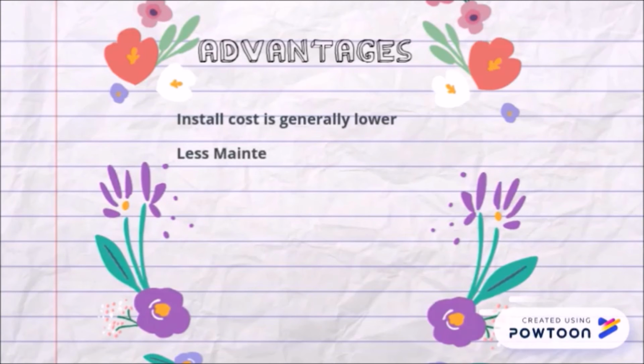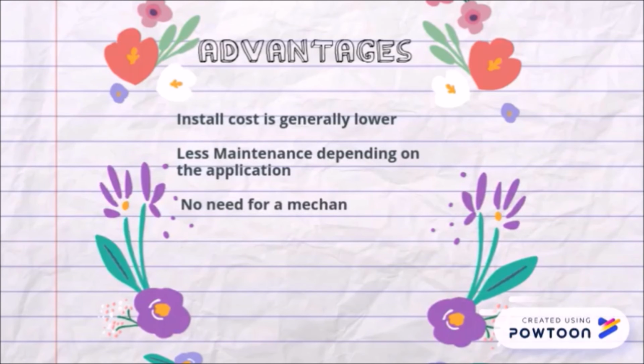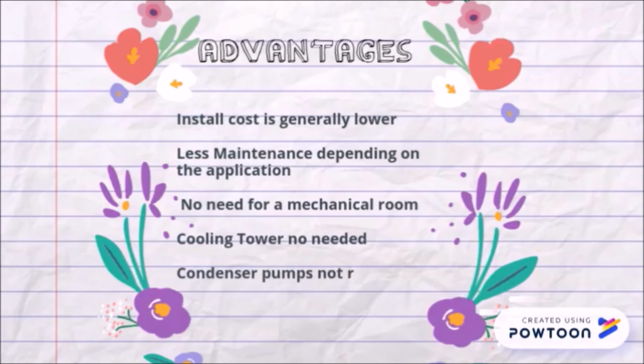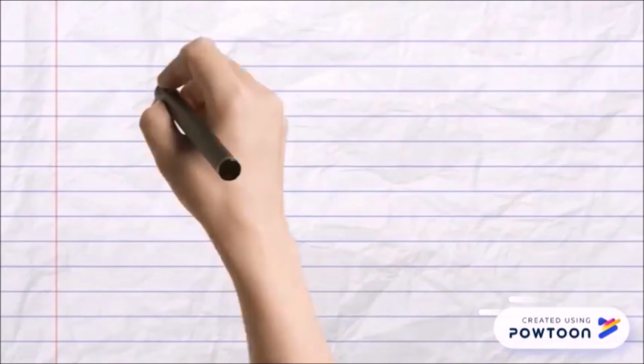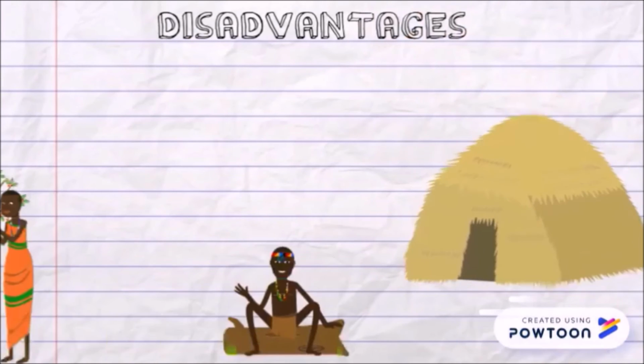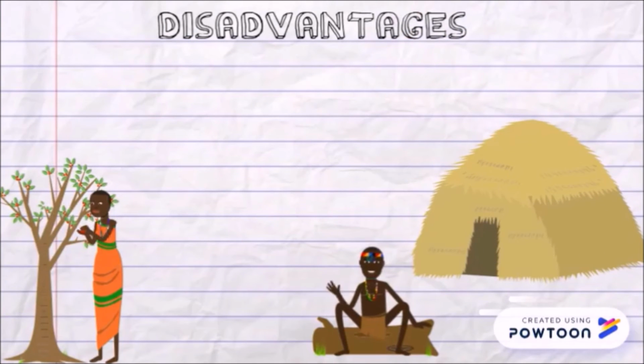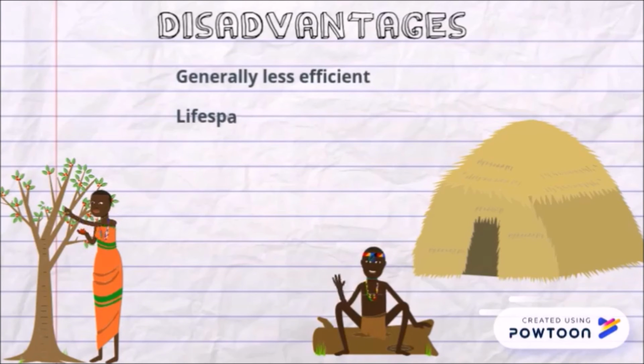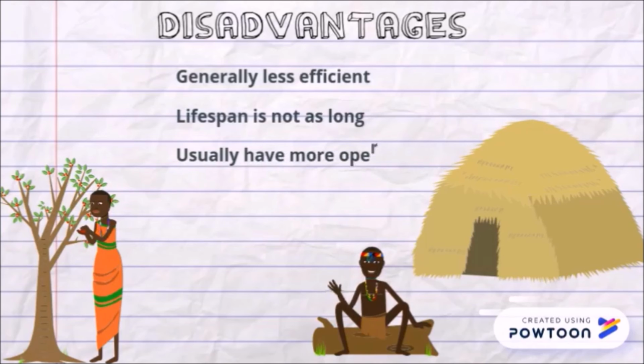Advantages of the air-cooled chiller. Install cost is generally lower. Less maintenance depending on the application. No need for a mechanical room. Cooling tower not needed. Condenser pumps not required. Disadvantages of the air-cooled chiller. Generally less efficient. Lifespan is not as long. Usually has more operating noise.